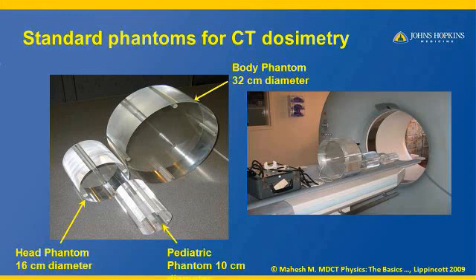Hello, we are going to talk about CT dose. When you say CT dose to a patient, there is actually no direct measurement on the patient. In fact, the CT dose is estimated based on phantoms. Phantoms are representative of the body and head size, and they are used by the physicist to measure radiation doses from which we estimate the patient dose.